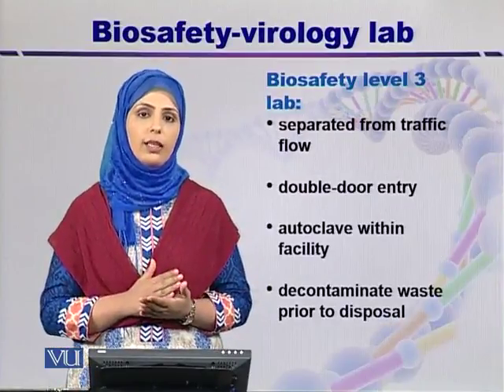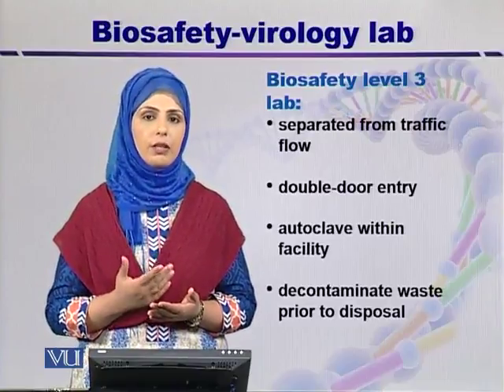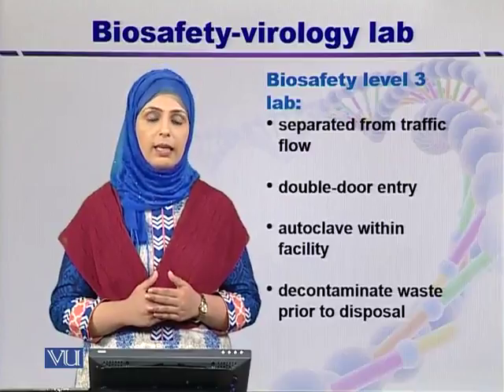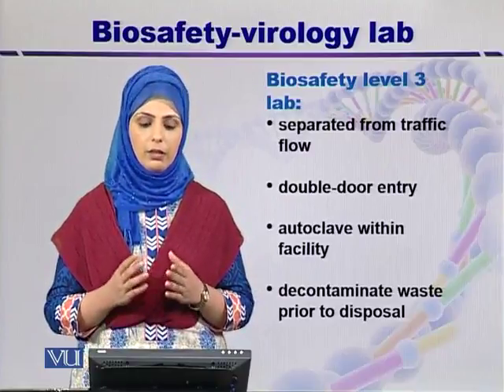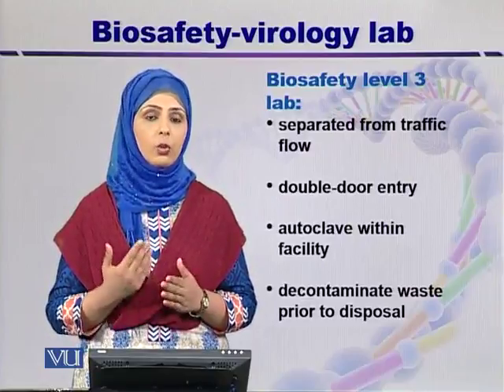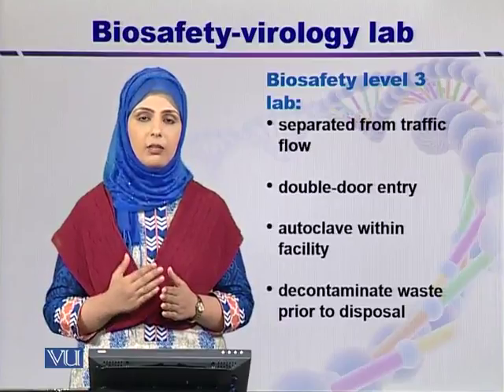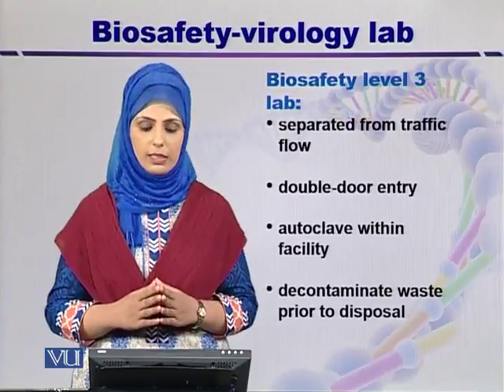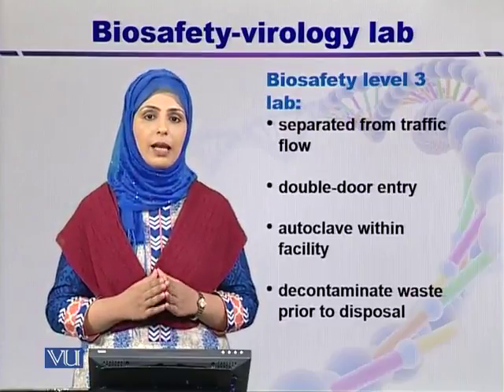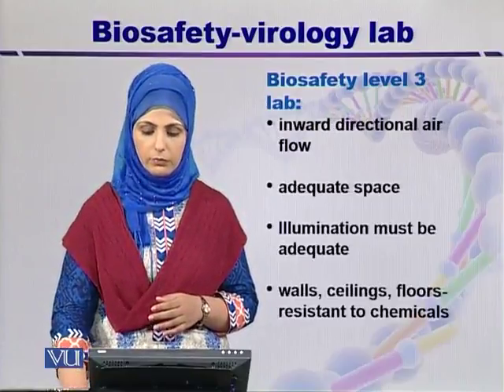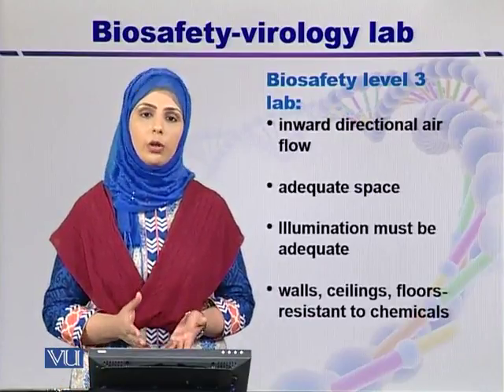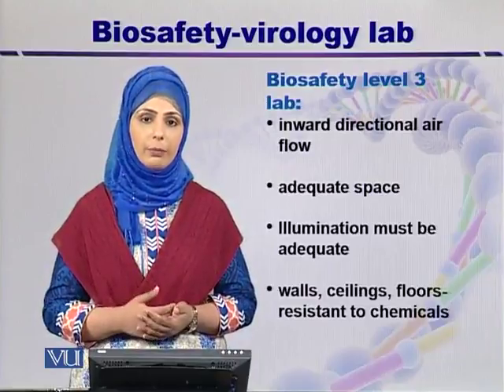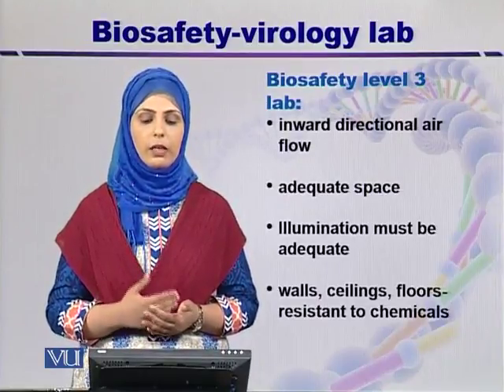Every virology lab follows biosafety level 3 standards. It should be separated from traffic flow, with interlocking double-door entry restricted to authorized persons only, and exit from the other side. An autoclave within the facility is recommended for decontaminating waste prior to disposal. Airflow is very important — whether performing open bench work or using a biosafety cabinet, the direction of airflow must be inward.